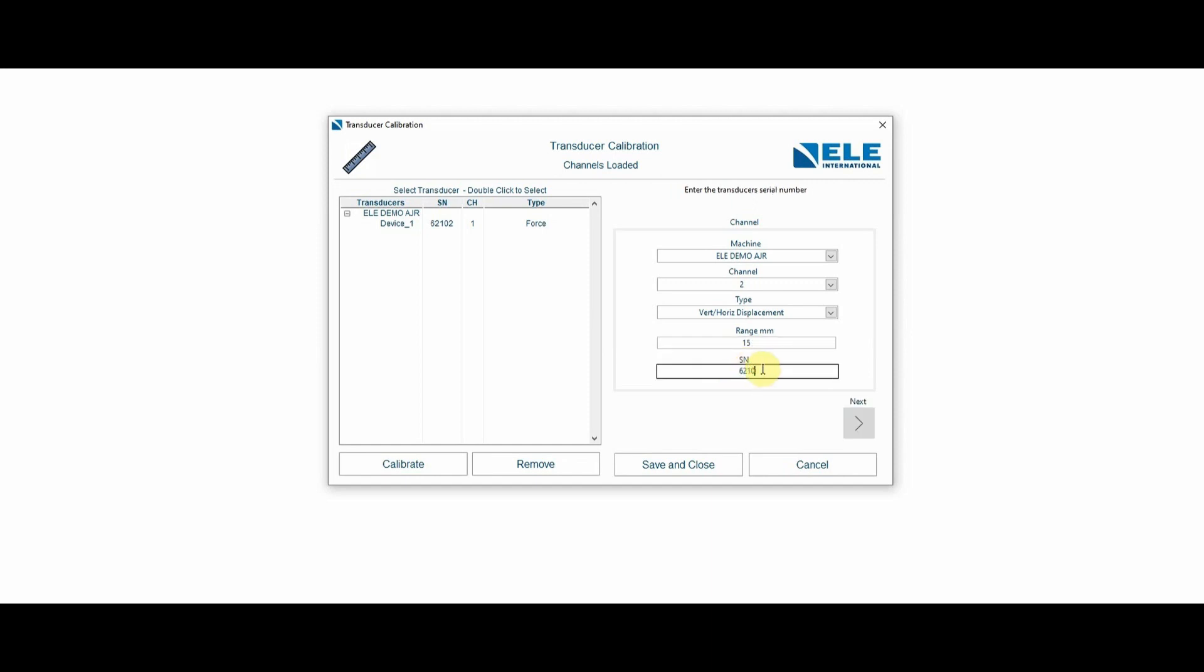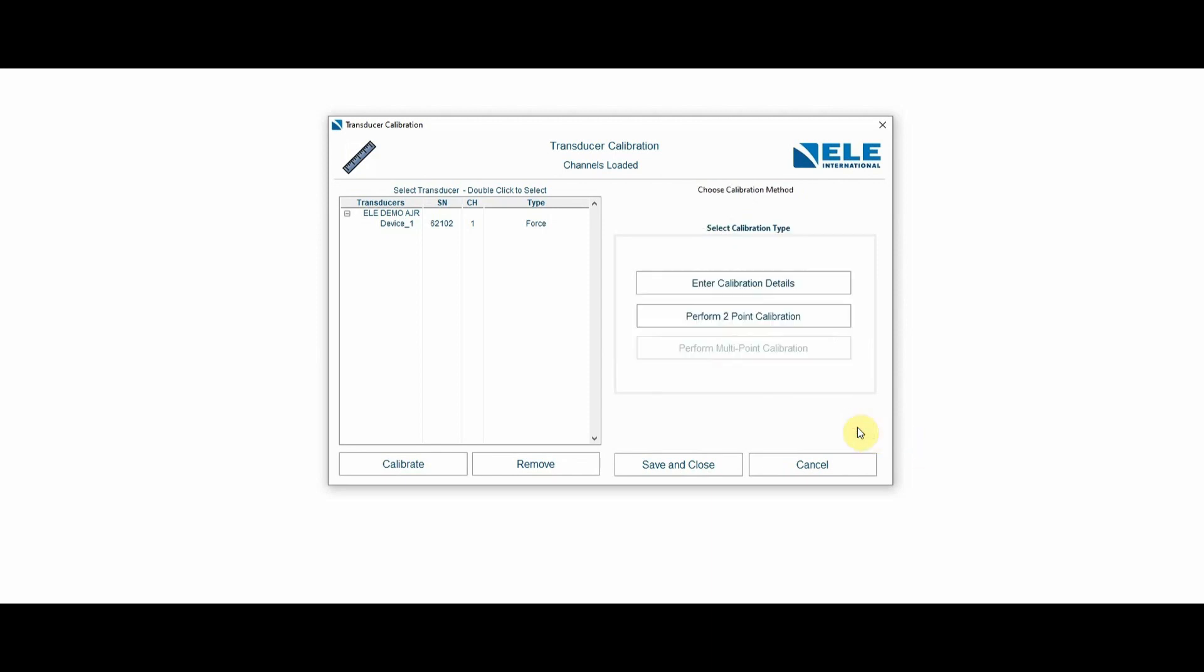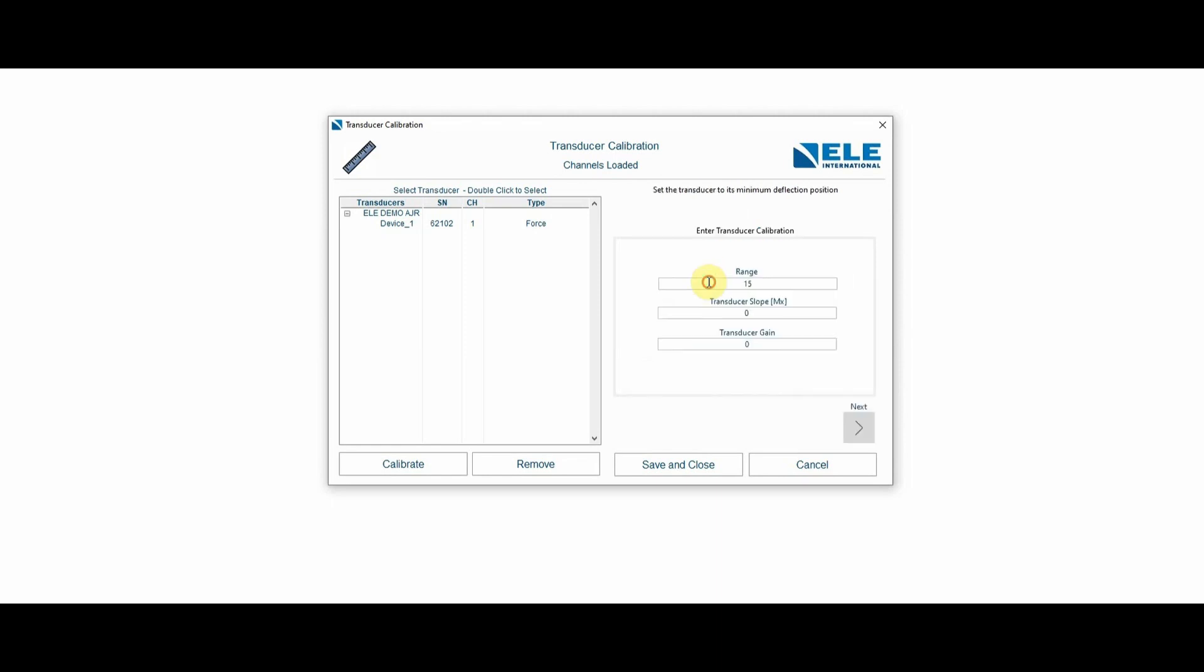It has a serial number per the certificate as I'm entering here. Again, I'm going to enter the calibration details. Otherwise, I can perform, if I had gauge blocks, I can perform a two-point calibration. In this case, I'm just going to enter the details that were provided to me.